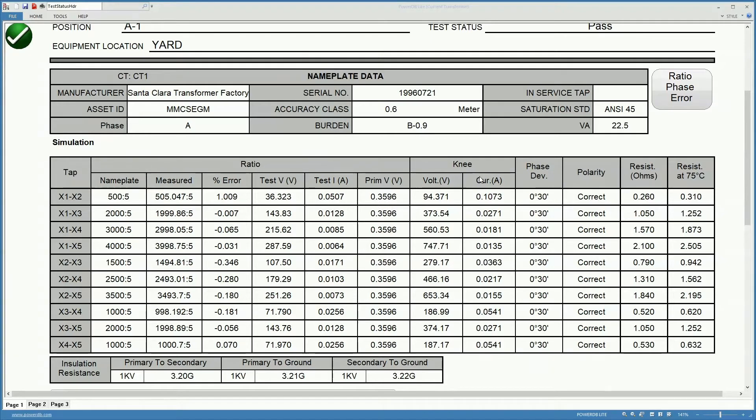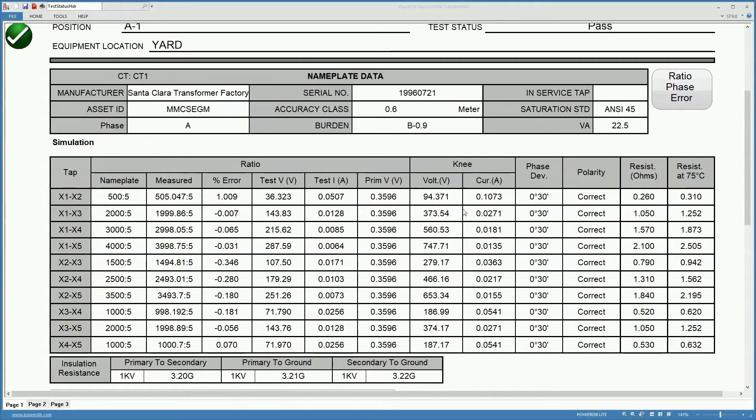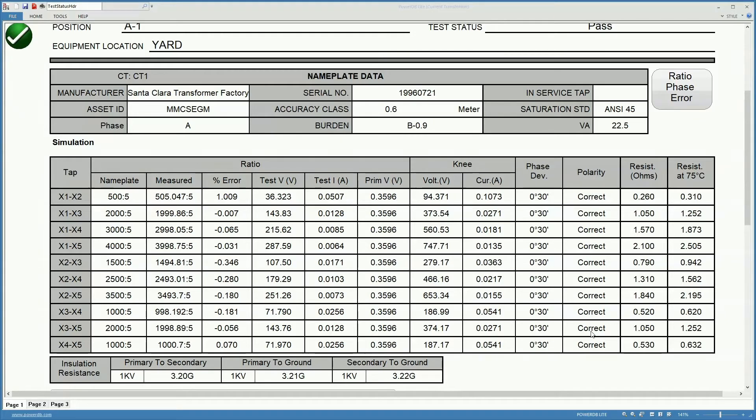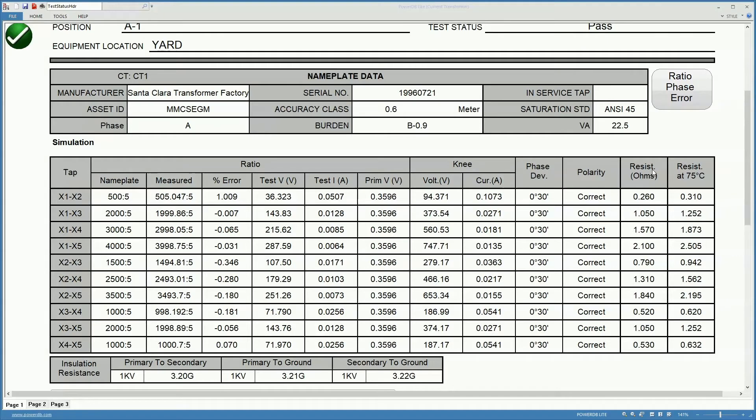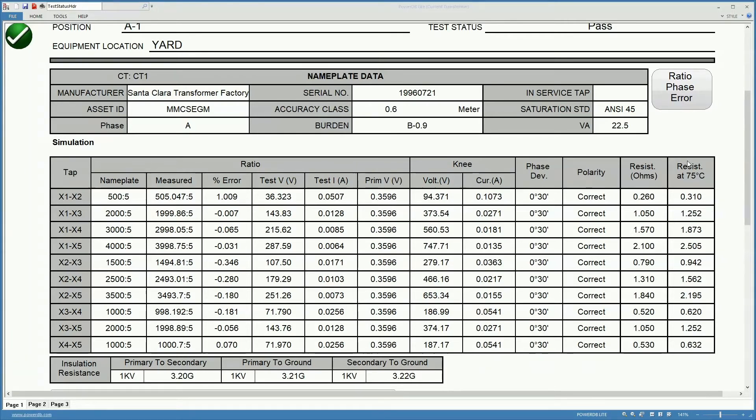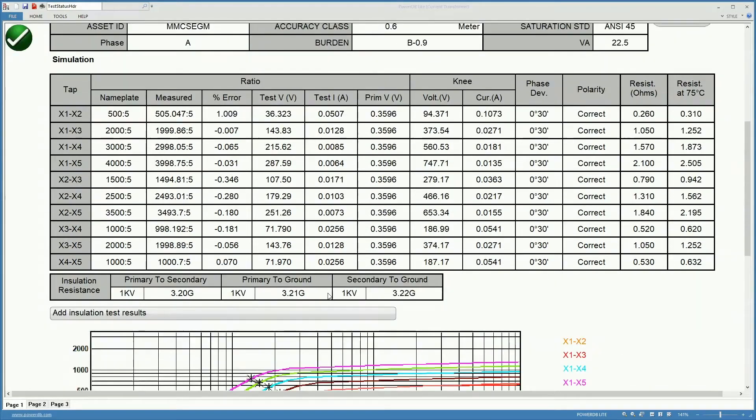We also get information on the knee point of the different curves. We get the phase deviation and polarity whether the polarity is correct or incorrect. We get the resistance since we did a full test. We also get the winding resistance and we get the resistance corrected at 75 degrees Celsius.